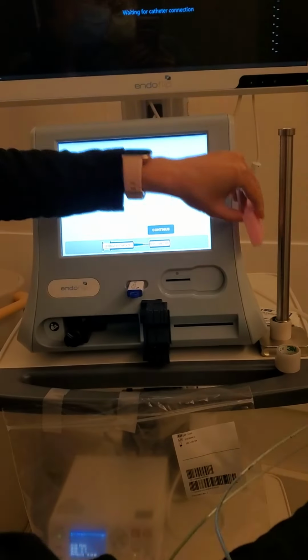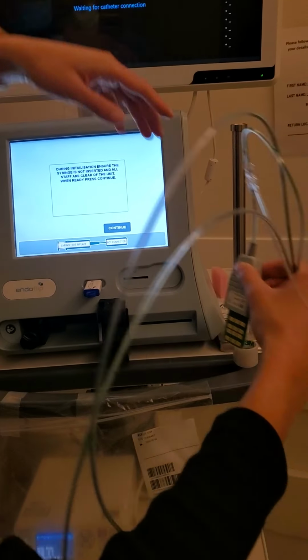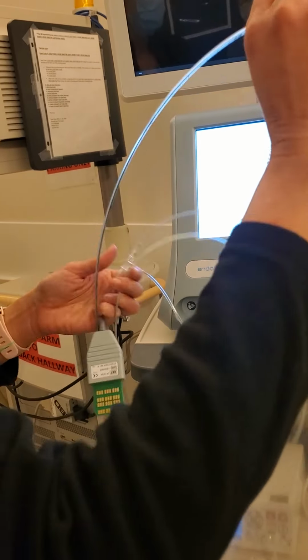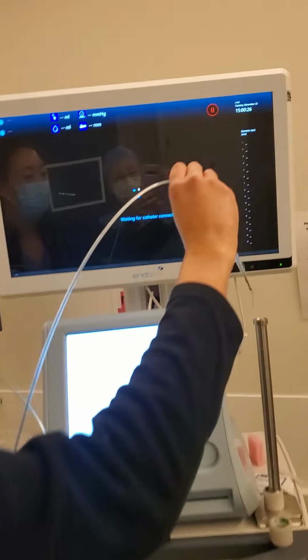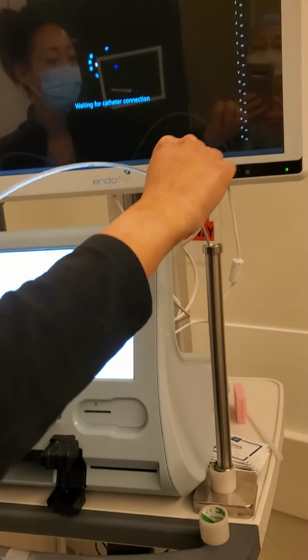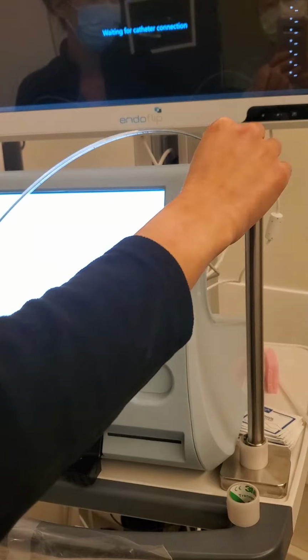The other thing you want to take off is this pink spongy thing. This protects the catheter electrode card in the packaging as well. So you want to take this. Protective sleeve is off. It's just the bare balloon. You're going to put it all the way into this calibration tube, all the way down to the bottom.